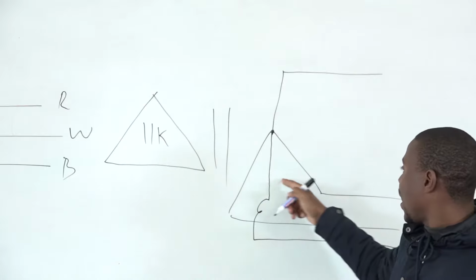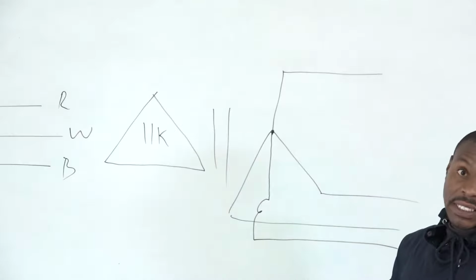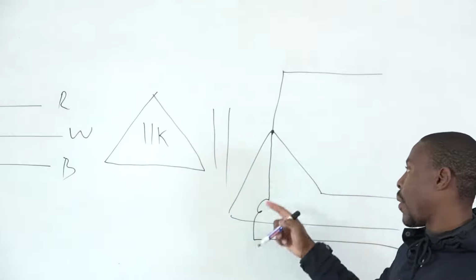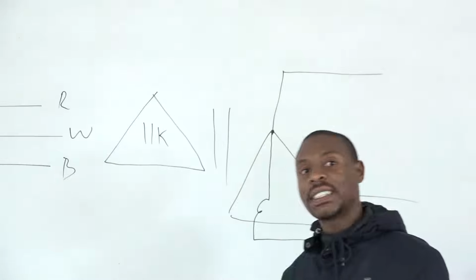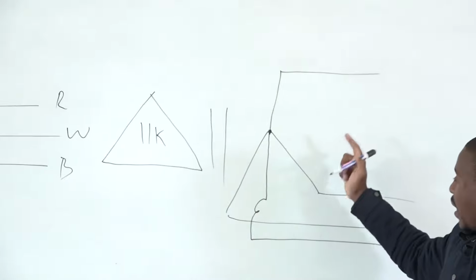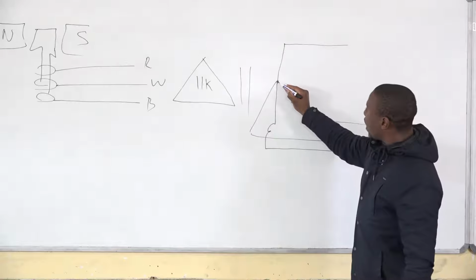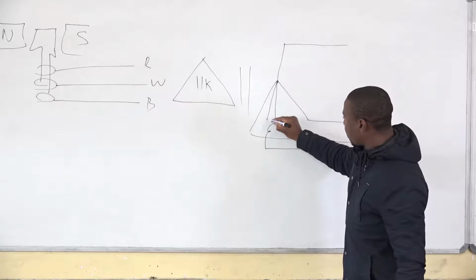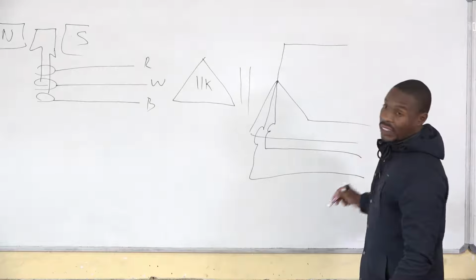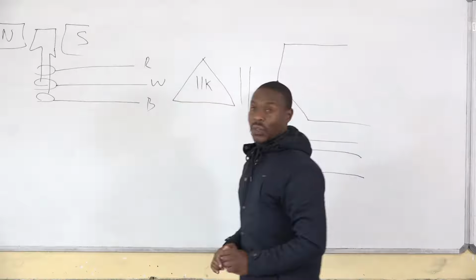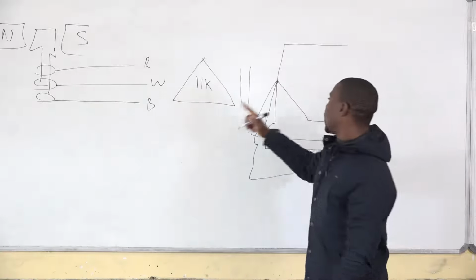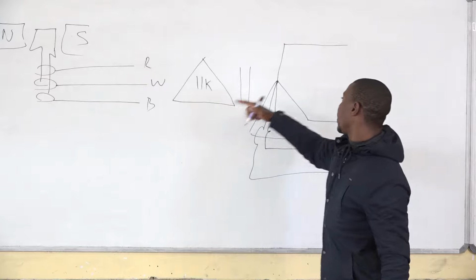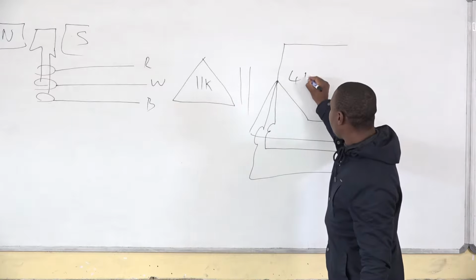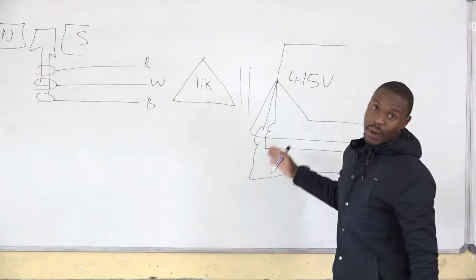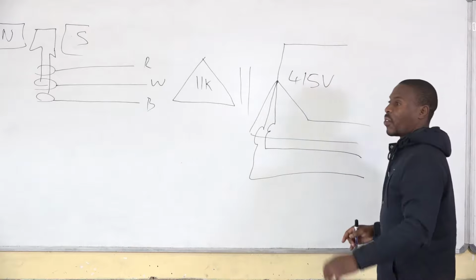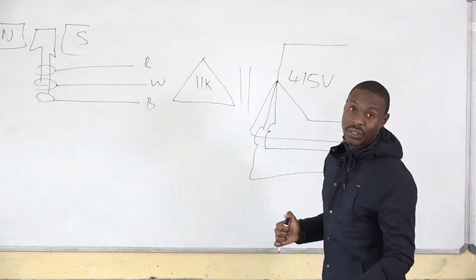Then from the neutral, we now have a 3-phase 4-wire system, but we also need an earth wire. Why are we earthing the neutral? For faults. If there are faults, they should go through an earth. Then we have the fifth wire, which is earth. That's how we get our 3-phase 4-wire system. So now, because we have a transformer, which we said is 11 kV to 415 volts, we need to balance a load from this 415 volts for commercial or domestic use.